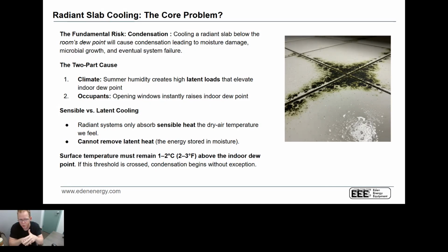From a climate standpoint, summer humidity creates high latent loads. This can elevate the indoor dew point. And the other one is occupants, right? We can't control occupants. I can remember people reaching out to me about heating, saying, can you come up with a control strategy that turns the heating off, because we have rental properties and they'll show up and for whatever reason, they'll just open the windows, even though the heat is on. You have to keep the human element in mind.